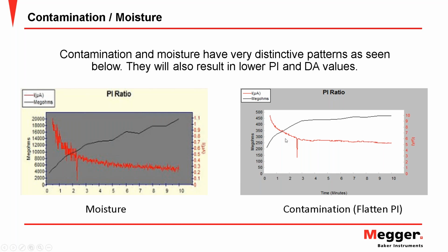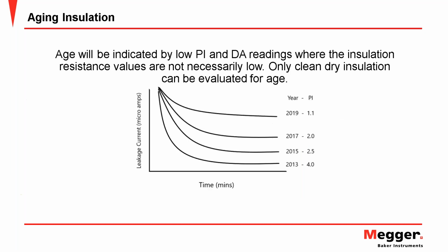Over here on the right, we see the effect of contamination, and specifically the type of contamination that's giving a surface leakage path around the insulation system, where it flattens out the curve in such a way that the insulation isn't really being measured anymore. We're just seeing the sustained level of current because of a parallel path caused by that contaminant from the conductors to ground. So again, a lot of value in this low voltage stuff, but this isn't stressing the insulation anyway. It's just quantifying the resistance to ground.